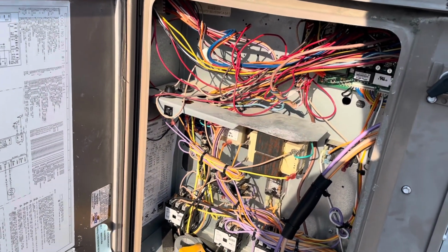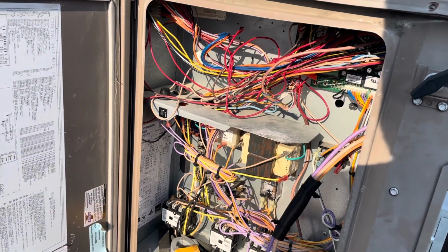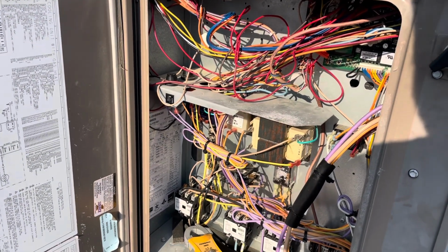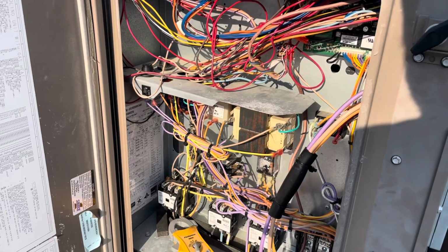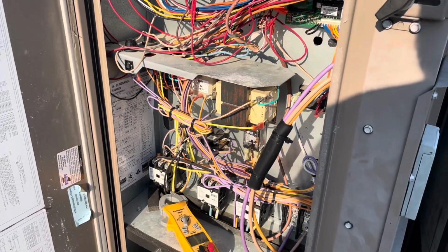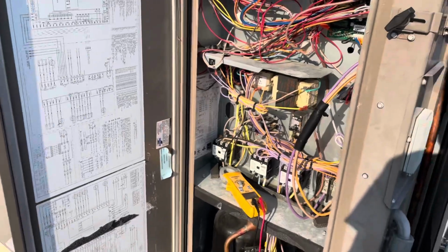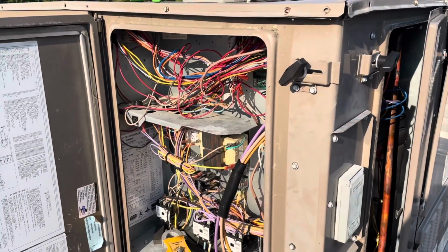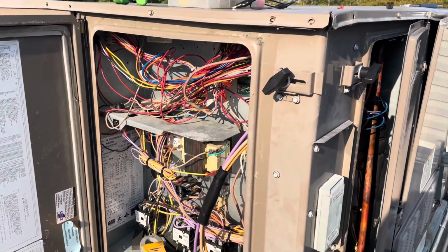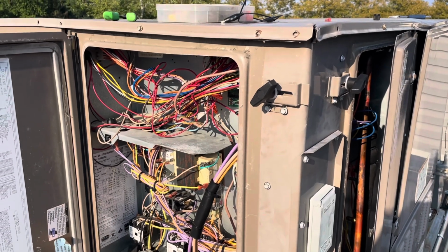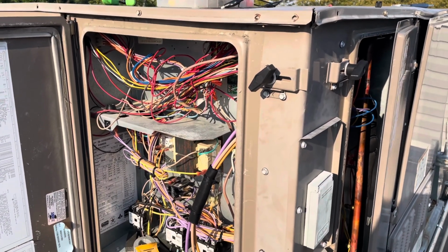But it doesn't matter if circuit 2 was hooked up or not. If it goes into a low pressure lockout, it will shut the whole system down. The system doesn't know or care if you have it wired, all it knows is its pressure switch opened and that's bad. So it'll shut itself down.